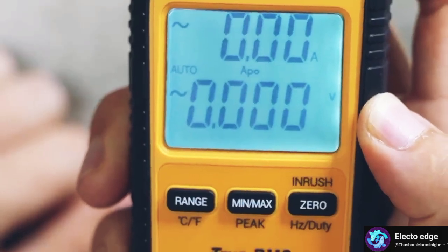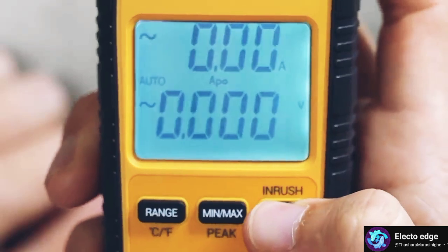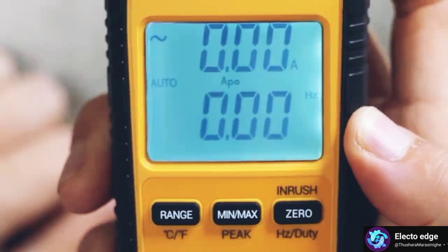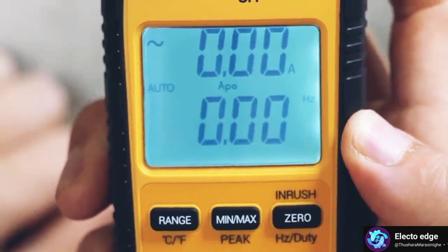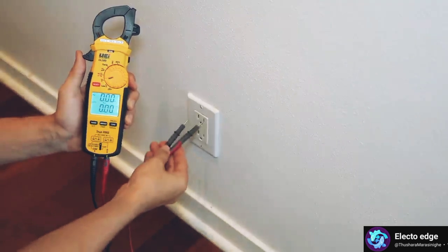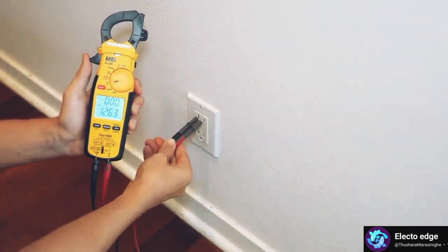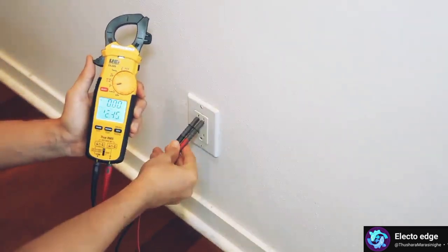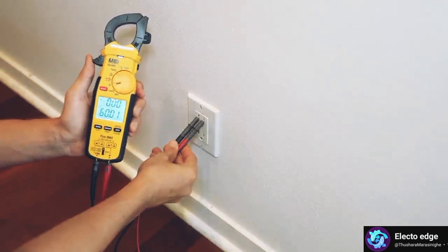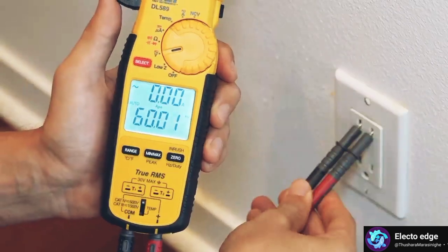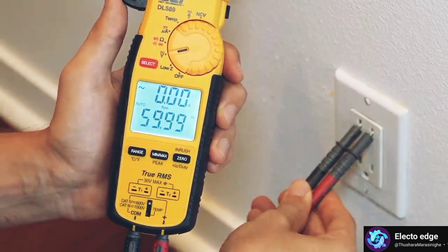Next up, we have Hz, which measures frequency. And frequency is the rate at which current changes direction per second. In America, the frequency we use is 60 Hz, but in many other parts of the world, such as Australia, China, and Germany, they use 50 Hz. Frequency is only measured with alternating current, and an easy way to check it is to simply stick your meter leads into a power outlet and see what you get. You should have exactly 60 or something very close to it.